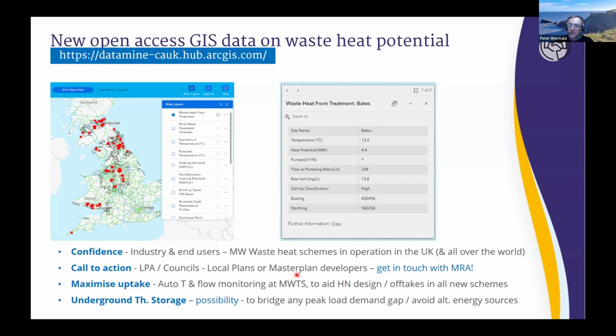And as part of our drive to maximize uptake of waste mine water heat, we've installed temperature and flow monitoring at key mine water treatment schemes to aid heat network design, and we're providing offtakes to all new schemes. Looking into the future, we've started to think about and work with colleagues such as the BGS around underground thermal storage as a possibility to bridge any peak load demand gap and avoid alternative energy sources.